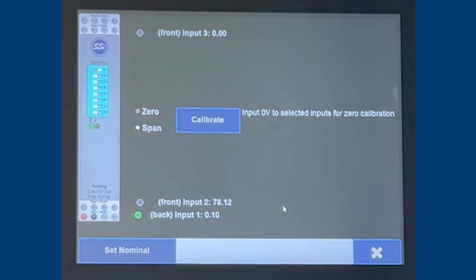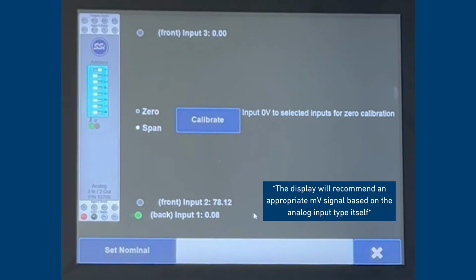We can now monitor this and watch for the update from the calibration process to be displayed. It may take up to 30 seconds. There's our update. Next, if we want to span calibrate the input, we would select span. It is going to then look at the input we have selected and see what the input is set for. If it is a TC or a voltage. In this case, input 1 is set for K thermocouple, so we need to now source in 72 millivolts to this input.